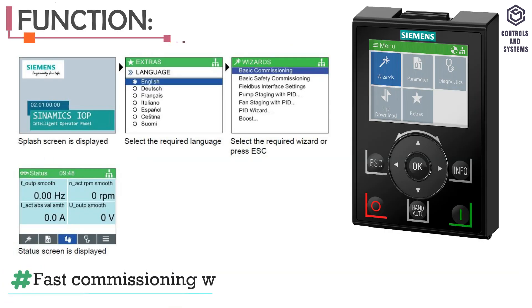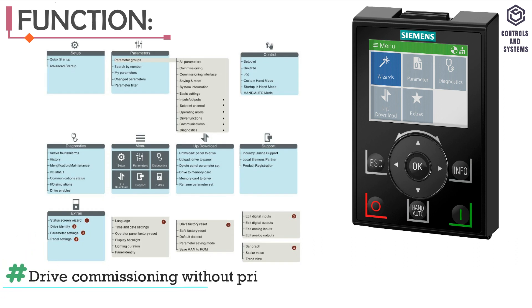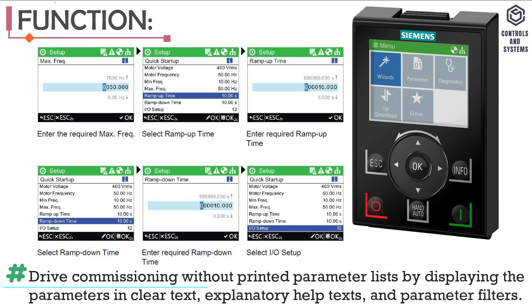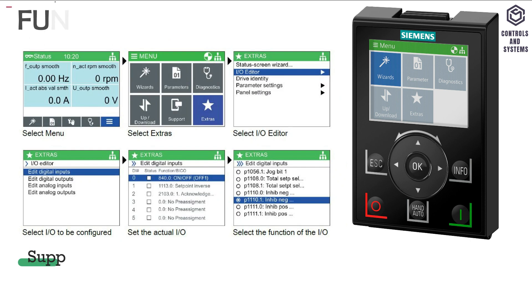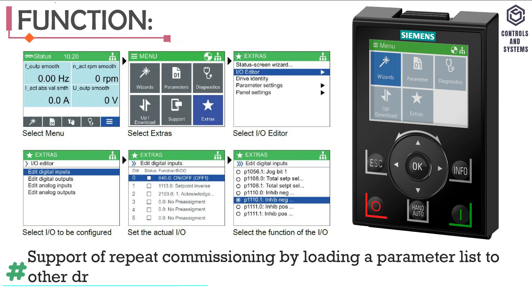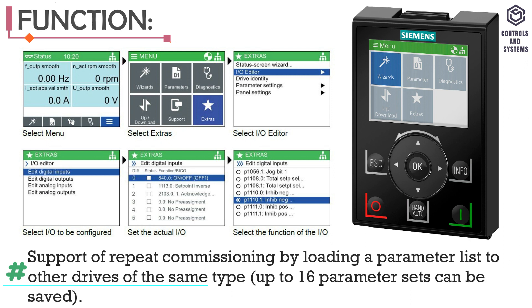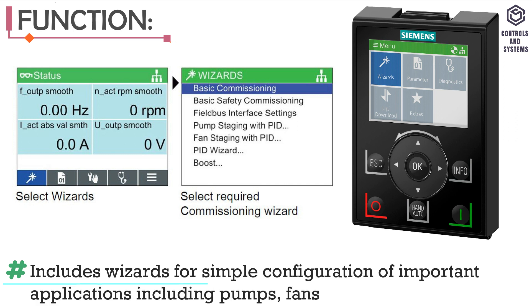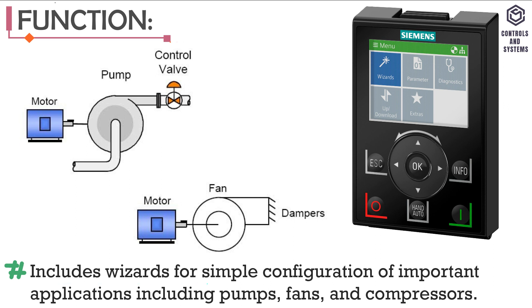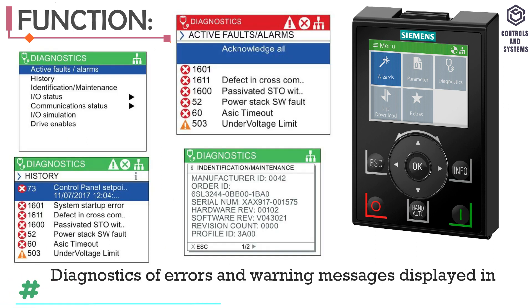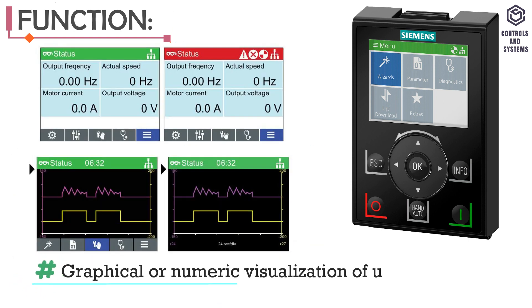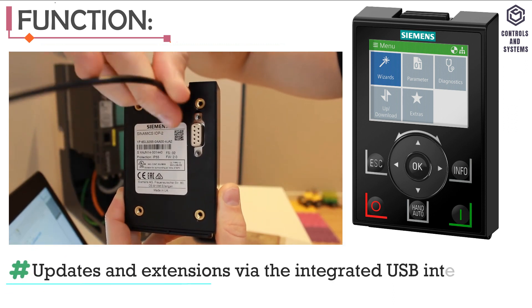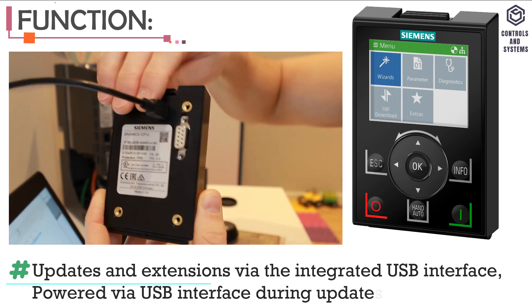Functions: Fast Commissioning Wizard for general commissioning; drive commissioning without printed parameter lists by displaying parameters in clear text; explanatory help texts and parameter filters; support of repeat commissioning by loading a parameter list to other drives of the same type; up to 16 parameter sets can be saved; wizards for simple configuration of pumps, fans, and compressors; diagnostics of errors and warning messages in clear text; graphical or numeric visualization of up to two process values; updates and extensions via integrated USB interface; powered via USB interface during updates.